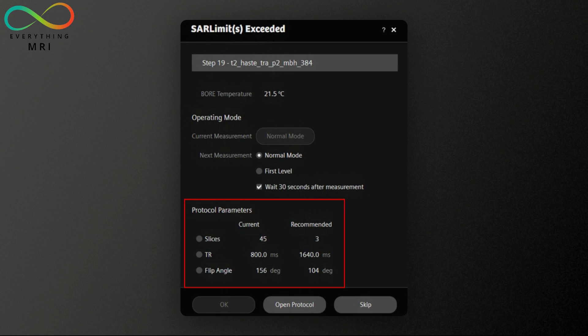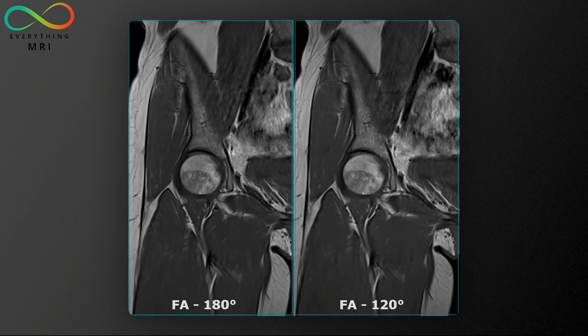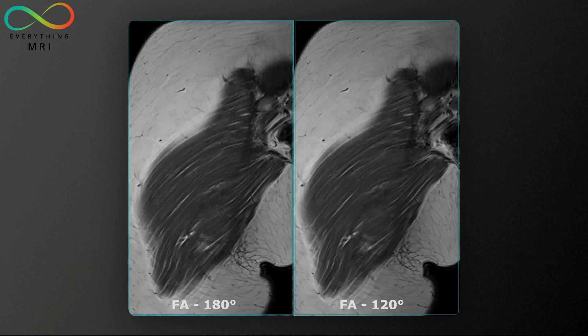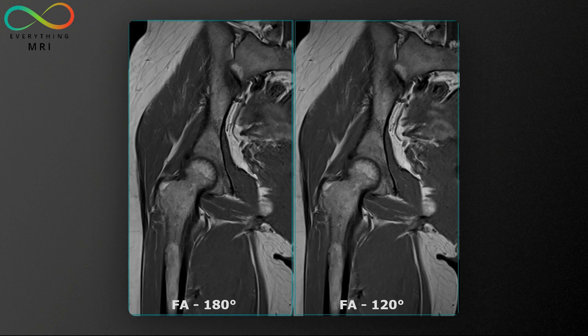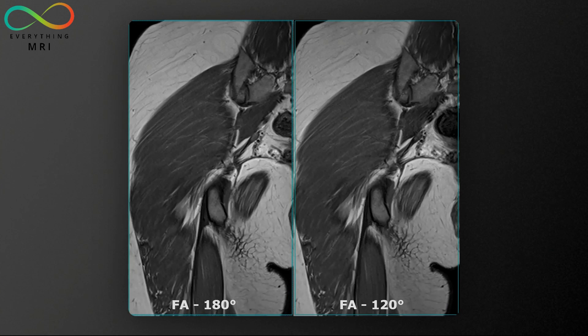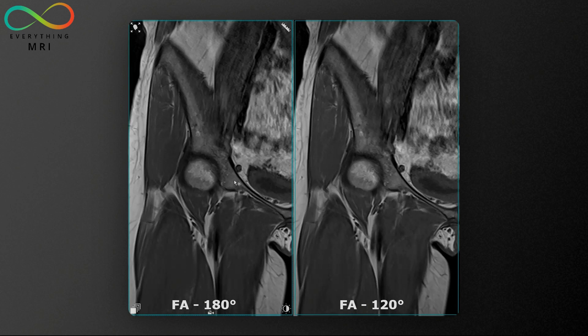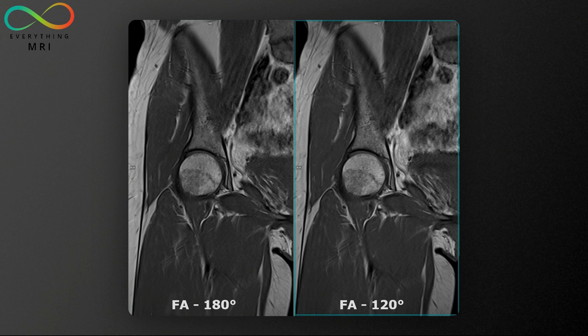The flip angle, in my opinion, is the first parameter to consider to get rid of these conflicts and avoid workflow disruption. When we talk about the flip angle, we refer to the angle at which the spins of protons are tipped away from their equilibrium state by a radio frequency pulse. Energy deposition increases with the square of the flip angle, so a 180° refocusing pulse deploys four times more energy than a 90° pulse.